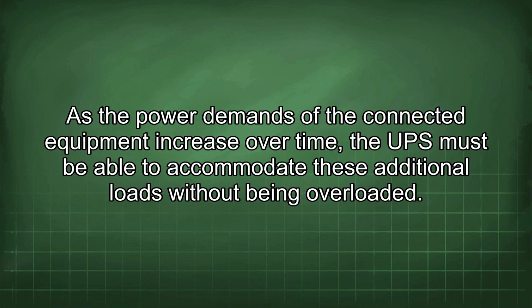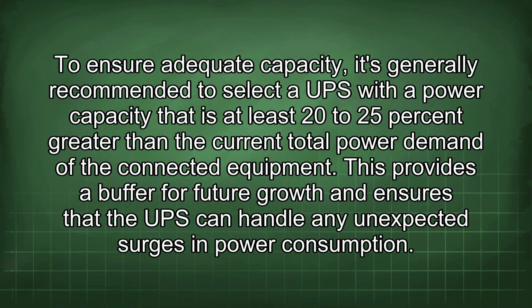As the power demands of the connected equipment increase over time, the UPS must be able to accommodate these additional loads without being overloaded. To ensure adequate capacity, it's generally recommended to select a UPS with a power capacity that is at least 20 to 25% greater than the current total power demand of the connected equipment. This provides a buffer for future growth and ensures that the UPS can handle any unexpected surges in power consumption.